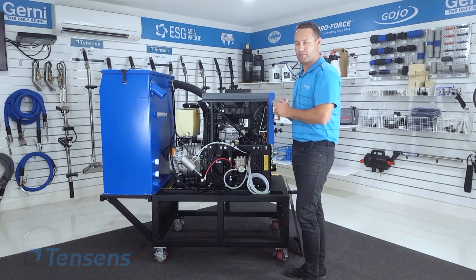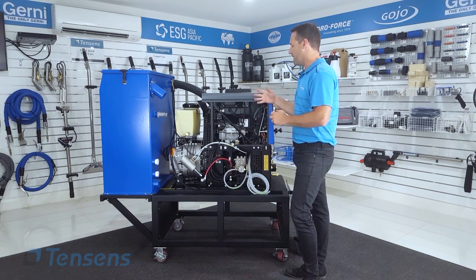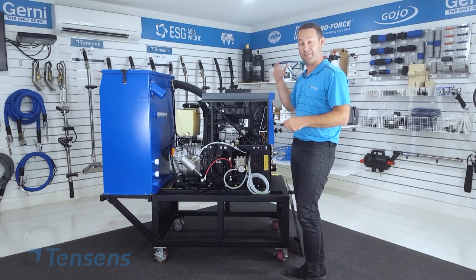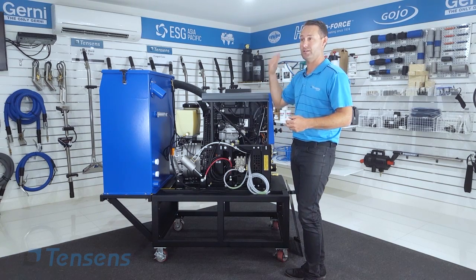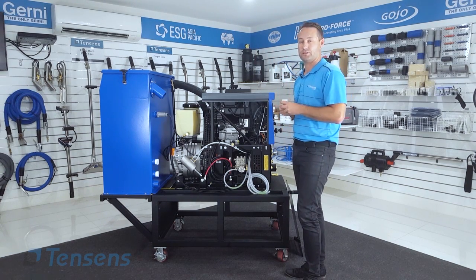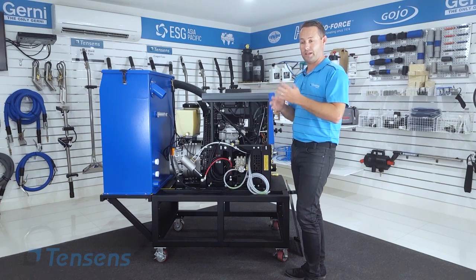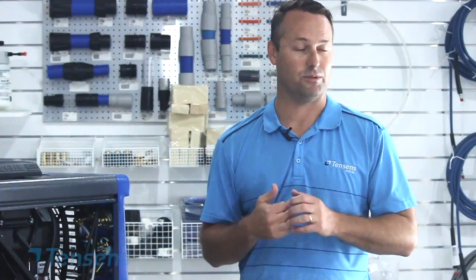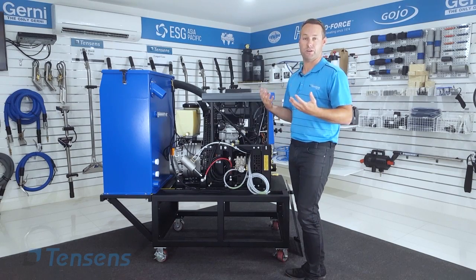The major one I would recommend probably getting us to do. As part of the major service, we would pull the heat exchangers out and give them a clean, get the carbon off the heat exchangers. I showed you before what the heat exchangers look like. You do need to give them a clean because you are getting carbon on them. So that's your 500-hour service, and that's something we can do or we can teach you how to do.